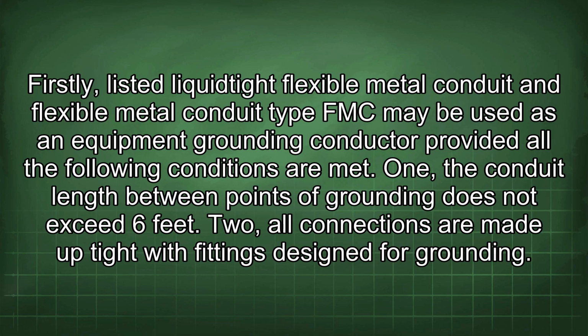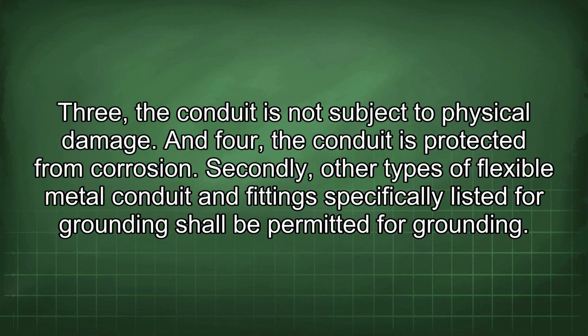1. The conduit length between points of grounding does not exceed 6 feet. 2. All connections are made up tight with fittings designed for grounding. 3. The conduit is not subject to physical damage. And 4. The conduit is protected from corrosion. Secondly, other types of flexible metal conduit and fittings specifically listed for grounding shall be permitted for grounding.